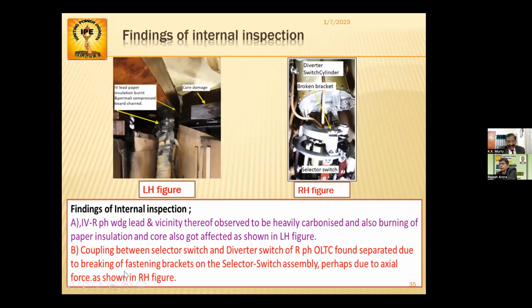And about this, coupling between selector switch and diverter switch of R-phase OLTC found separated. This is the MR type tap changer. MR type tap changer has got two portions. One is the selector switch and the other is diverter switch. So selector switch is inside the transformer, whereas the diverter switch comes up on the top of the transformer.